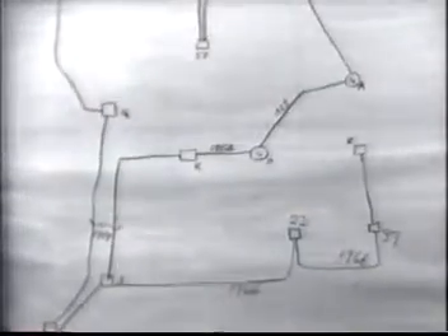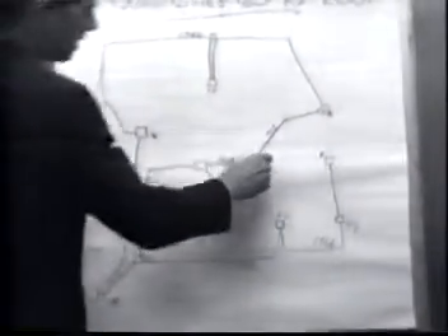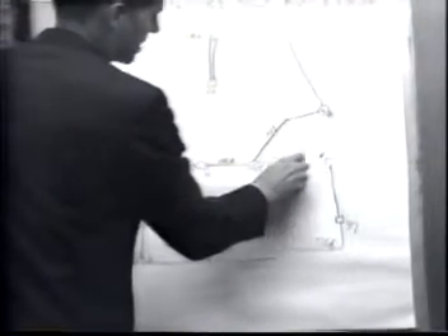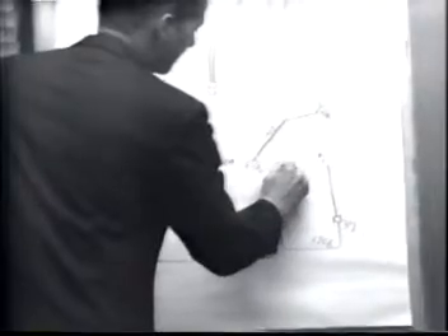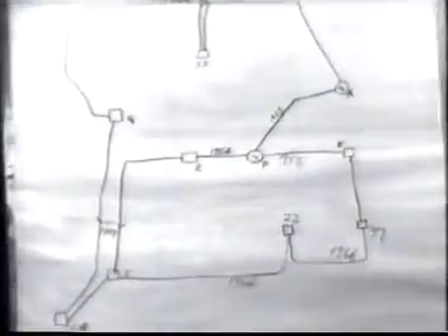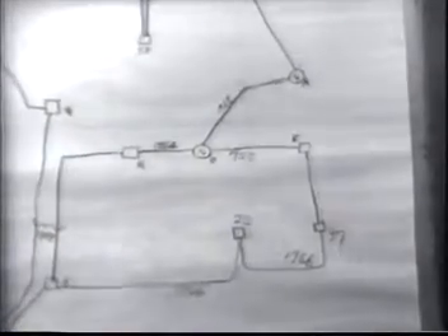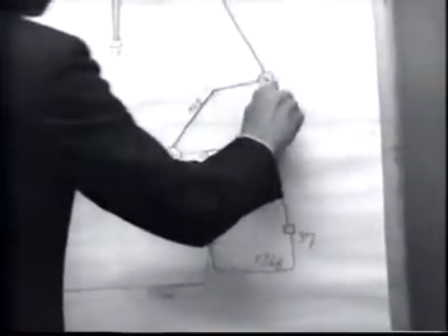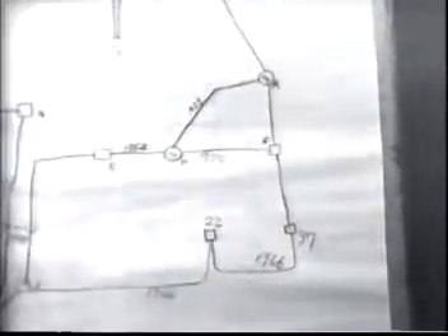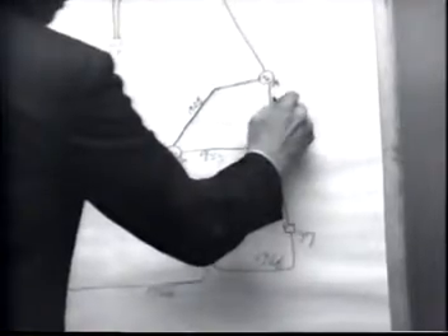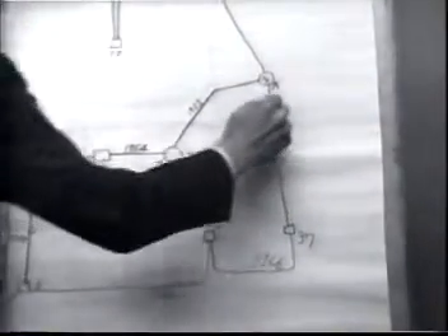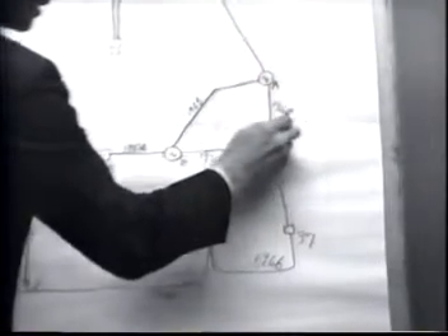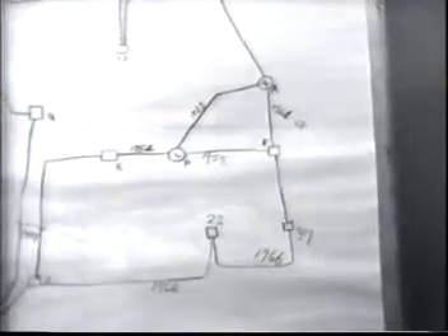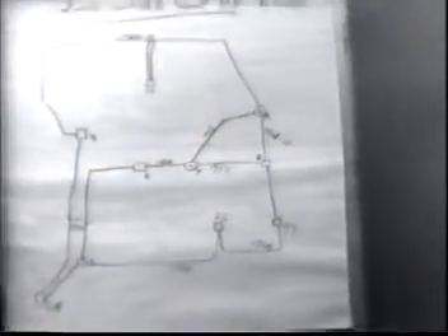Now, previous to this time, in about 1955, a line was built from Moline Plant to Substation E, and when the last large steam unit was built at Riverside, an overhead line was built from Riverside to East Moline. This was a double circuit line. The first one was put in service in 1964, and the second line in 1968. So you can see we have several loops around the Quad Cities. This line here completed the southern loop. This completed another loop there.